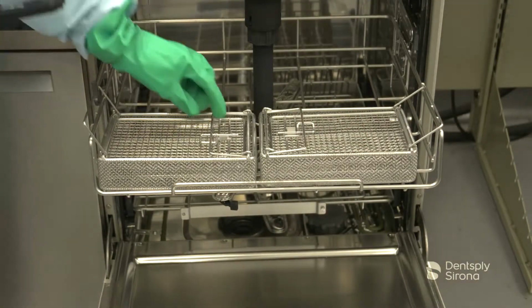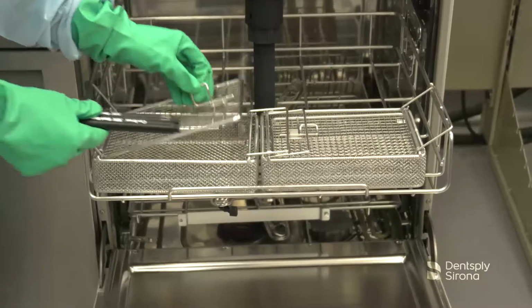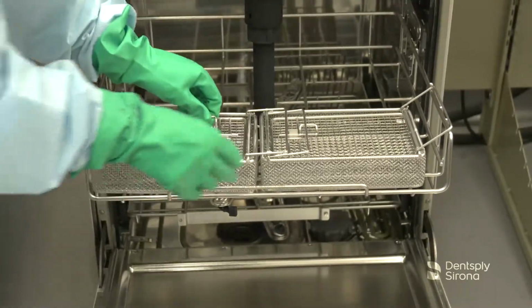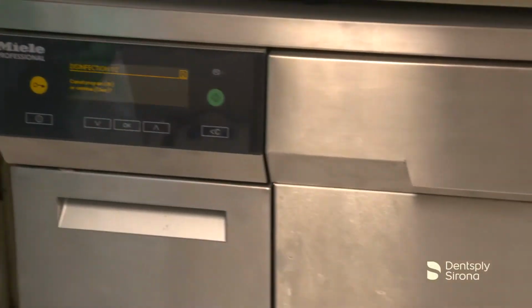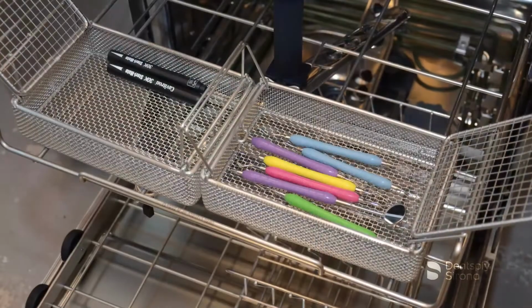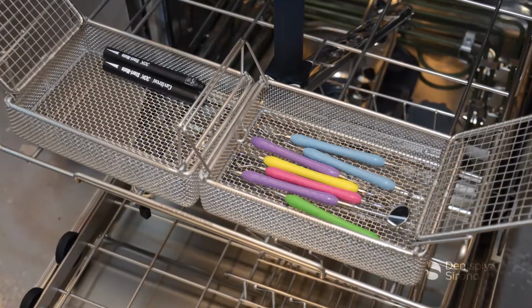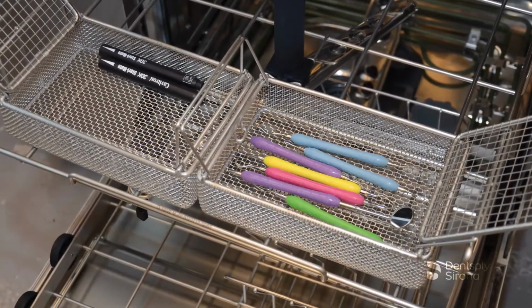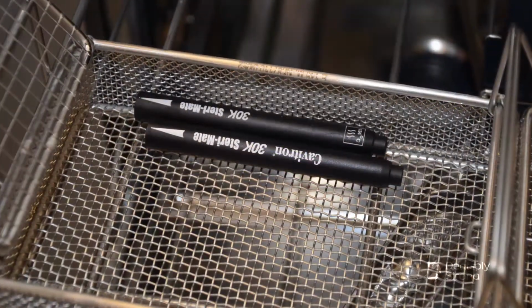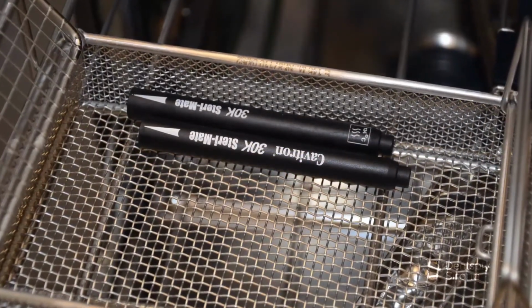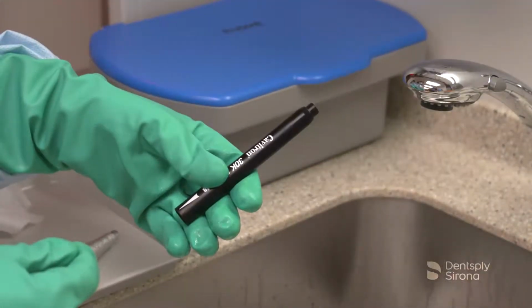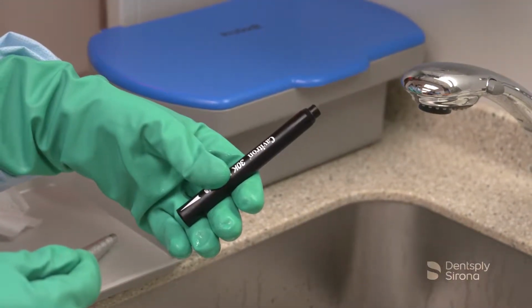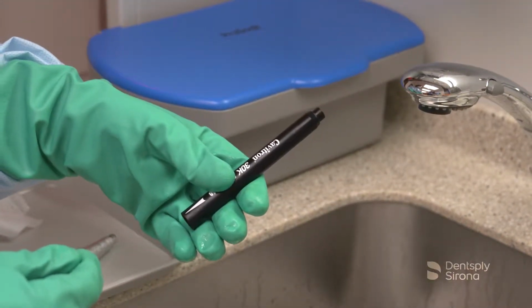Steri-Mate handpieces can be cleaned and disinfected in automated instrument washers. For cleaning and disinfection of these handpieces in an instrument washer disinfector, always follow the manufacturer's instructions for use for the unit and the instrument washer solution, making sure to observe the concentration rates and contact times, as well as the instrument washer's recommended cleaning and/or thermal high-level disinfection cycle. After the dry cycle is complete, always inspect for remaining debris. If debris is still visible, repeat the washer disinfector cycle.